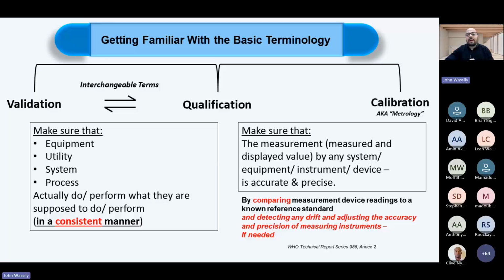By this, for example, if I'm talking about a sterilizing autoclave, its qualification will be about making sure that this sterilizing autoclave is actually performing and doing what it's supposed to do. It's actually giving us a product that is sterile and free from any microbiology or bacterial traces. So by qualification and validation, I mean making sure that the equipment, utility, system, or process is actually doing and performing as per the estimated and expected performance in a consistent manner. So every time that I will be operating my sterilizing autoclave, by doing some testing on it, I will be sure that finally it will give me a product that is sterile and free from any microorganism.